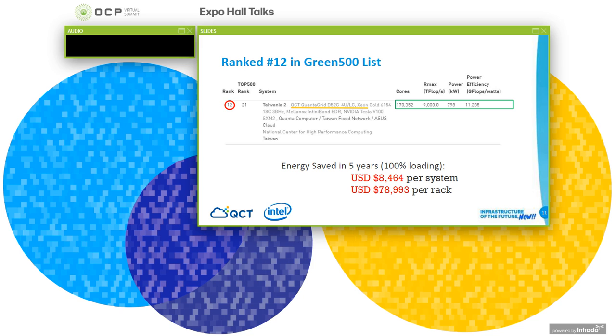With the liquid cooling technology, it is projected to save $8,464 per server during the 5-year life cycle of this system, which translates to savings of up to almost $79,000 for the whole rack, compared to using traditional air cooling technology.